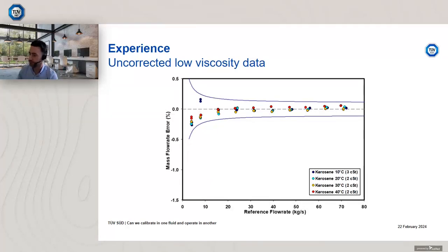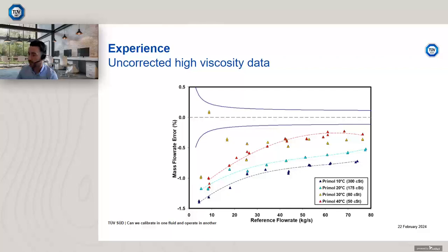The data looks good. Now what happens if we then apply that exact same meter in the same installation? In actual fact, the meter wasn't moved. We simply changed out the fluid from low viscosity to high viscosity. And you can see with the next set of data, and I've kept the same y-axis scale, so again from 0.5 to minus 1.5, this is with a fluid with the trade name Primol, but of more importance is the viscosity range, which is 50 to 300 centistokes depending on the temperature.